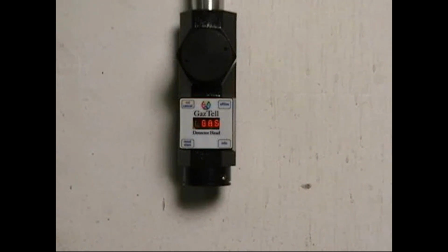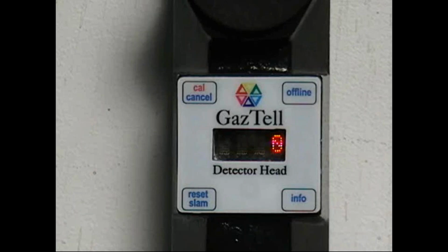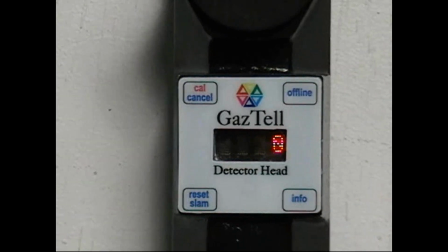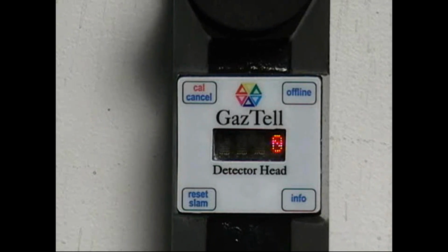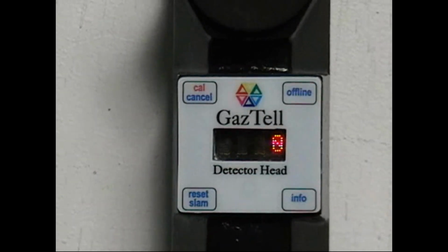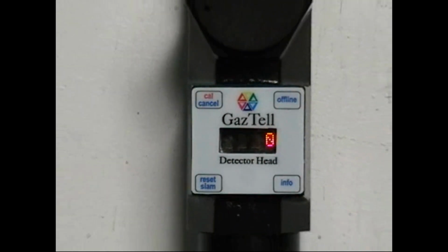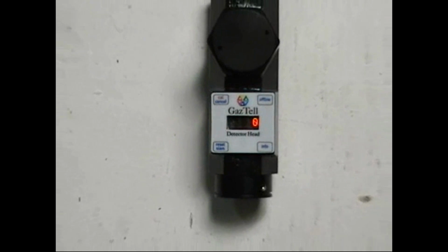The detector head will display the gas reading, but will not resume normal operation until the gas has dissipated to less than 5%. If the span calibration was unsuccessful, calibration error will be displayed indefinitely. To clear this, hold the blue end of the calibrator over the cancel mark for 5 seconds. The detector head will return to its original span value and will need to be performed again. An unsuccessful calibration may indicate an erratic sensor or bad span gas. You should make more than one attempt to calibrate span. Please refer to the owner's manual for more specific detail and explanations on calibrating a GazTell 450 detector. This concludes the calibration portion of the GazTell 450 video.